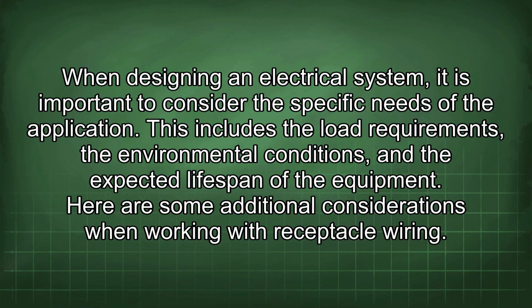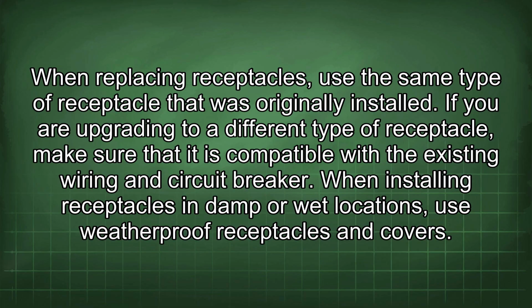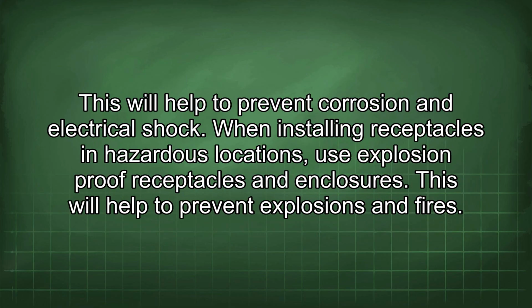Here are some additional considerations when working with receptacle wiring. When replacing receptacles, use the same type of receptacle that was originally installed. If you are upgrading to a different type of receptacle, make sure that it is compatible with the existing wiring and circuit breaker. When installing receptacles in damp or wet locations, use weatherproof receptacles and covers. This will help to prevent corrosion and electrical shock. When installing receptacles in hazardous locations, use explosion-proof receptacles and enclosures. This will help to prevent explosions and fires.